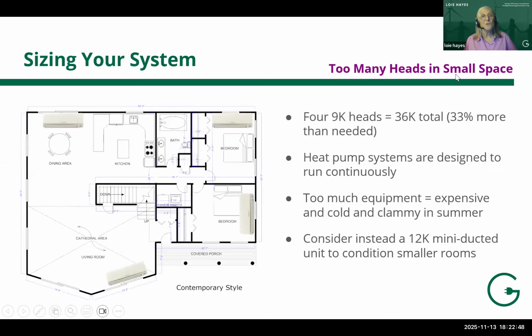where there are too many heads in too small a space, and the contractor has proposed four 9,000 BTU heads, which gives you a total of 36,000 BTUs. That's 33% more than what your heat load calculation called for. So you're buying too much equipment, and because heat pump systems are designed to run continuously at a steady pace, not ramping up and ramping down, there's going to be a real problem with them being too expensive to operate. And in the summer, it can be cold and clammy because the dehumidification happens slower than the cooling does.